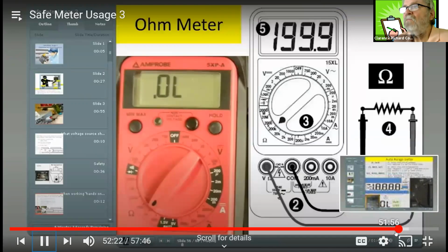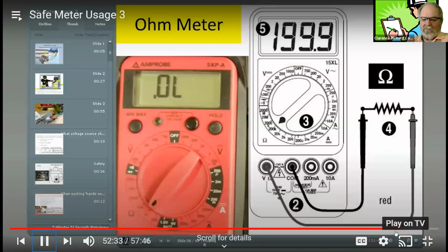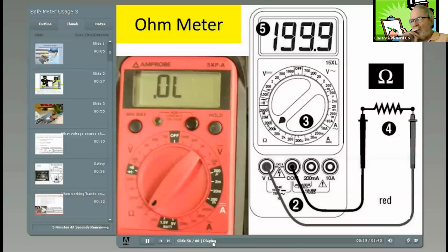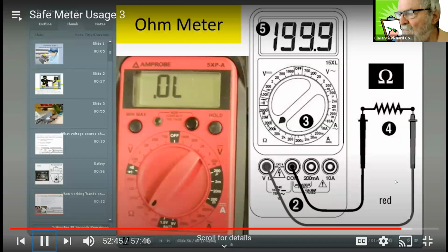Danger: do not measure voltage when meter is set to measure resistance. Turn off power to the resistance to be measured and discharge any capacitors. Any voltage present during a resistance measurement will cause inaccurate readings. Connect red test lead to volt-ohm input and black test lead to COM input. Set function and range switch to the desired ohm position. Connect test leads to resistance or circuit to be measured.